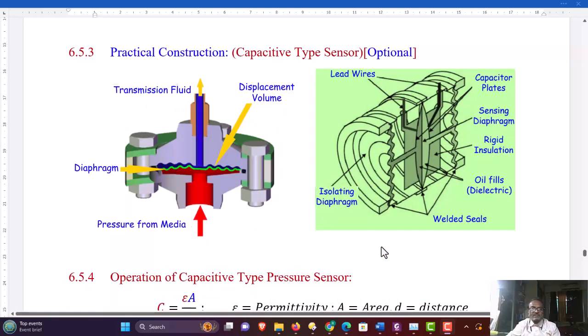A practical construction of a capacitive type of sensor is shown here. This is just for the sake of additional knowledge. This is optional from your syllabus point of view. So here this diagram indicates a corrugated diaphragm. The mechanical housing is provided and the fluid connection pipe is also shown, which allows the fluid connection to be done to the sensor, and the fluid is allowed to exert the pressure on the diaphragm.